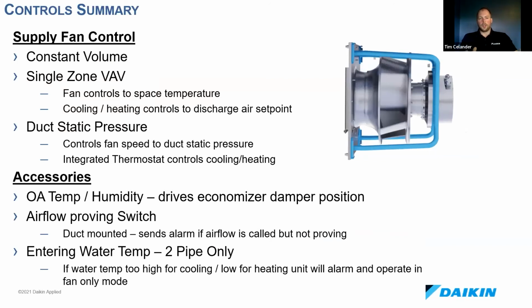So like I said, as we talk through what controls are, I like to talk through how you control an individual component and how that interacts with the system. So the supply fan options we have are constant volume, where it's running at a fixed speed. Two quick notes on that though. The integrated thermostat, you are able to turn down your fan speed. So if someone's too hot, too cold, they might go hit the fan button and reduce the speed in like 15% increments. You can also run temporary set points.